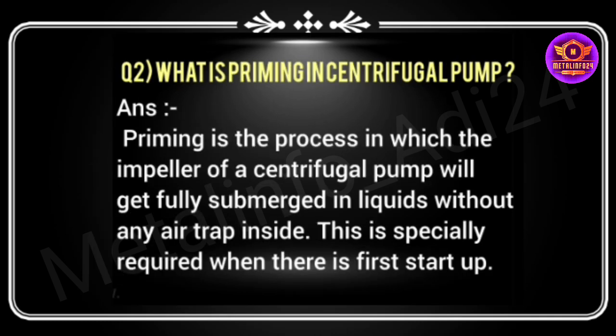दूसरा प्रश्न है, व्हाट इज प्राइमिंग इन सेंट्रीफ्यूगल पंप? प्राइमिंग is the process in which the impeller of the centrifugal pumps will get fully submerged in liquid without any air trap inside. This is especially required when there is first start up.